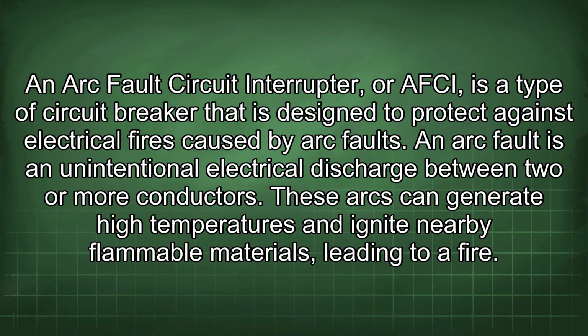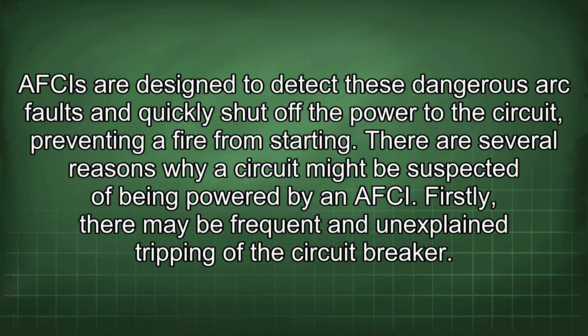An arc fault circuit interrupter, or AFCI, is a type of circuit breaker that is designed to protect against electrical fires caused by arc faults. An arc fault is an unintentional electrical discharge between two or more conductors. These arcs can generate high temperatures and ignite nearby flammable materials, leading to a fire. AFCIs are designed to detect these dangerous arc faults and quickly shut off the power to the circuit, preventing a fire from starting.